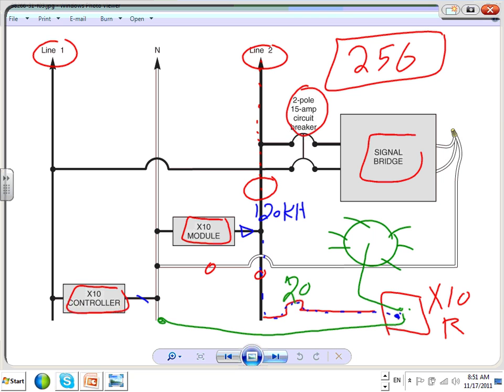This bridge is between the two hots, and also receivers. At the other end, you have to plug a receiver into the power line, right down to the receptacle. So you put all this right in the panel or around the panel, and you have the receiver right here, and there's no wire in between them other than the power lines. As long as they're tied to the power line, you're good to go. And it's not wireless. This is not wireless technology.